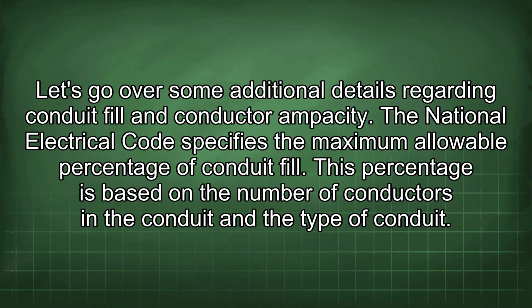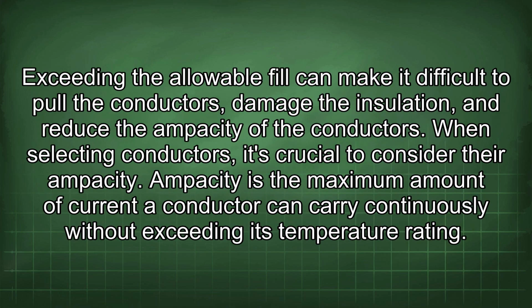Let's go over some additional details regarding conduit fill and conductor ampacity. The National Electrical Code specifies the maximum allowable percentage of conduit fill. This percentage is based on the number of conductors in the conduit and the type of conduit. Exceeding the allowable fill can make it difficult to pull the conductors, damage the insulation, and reduce the ampacity of the conductors.